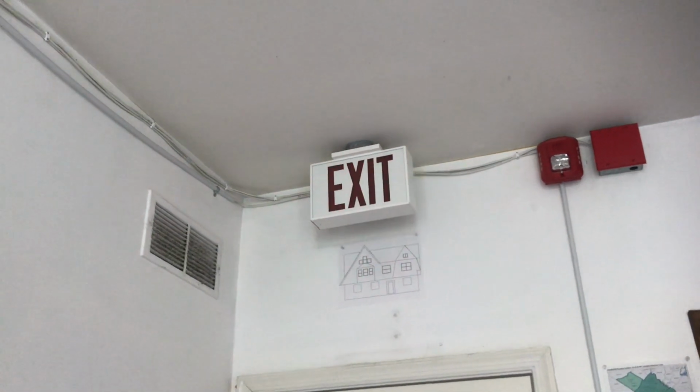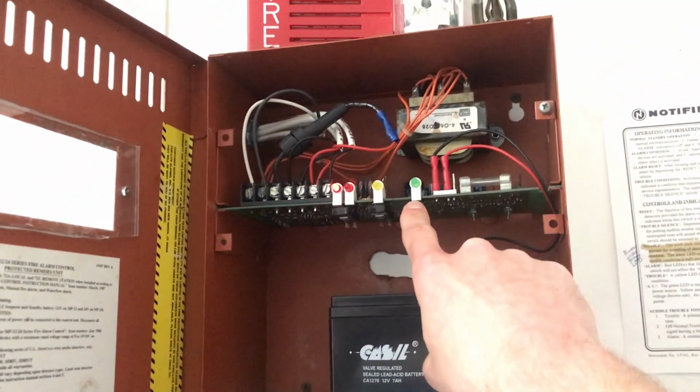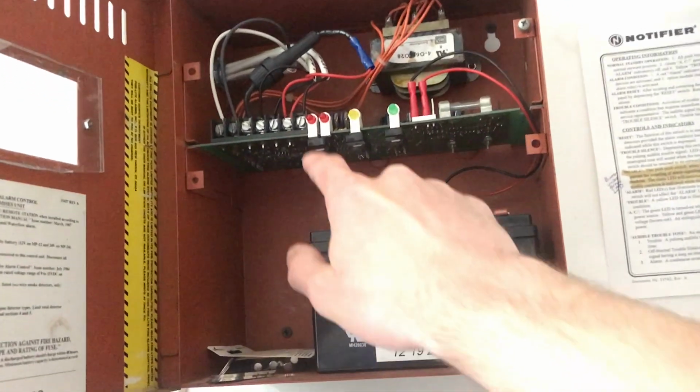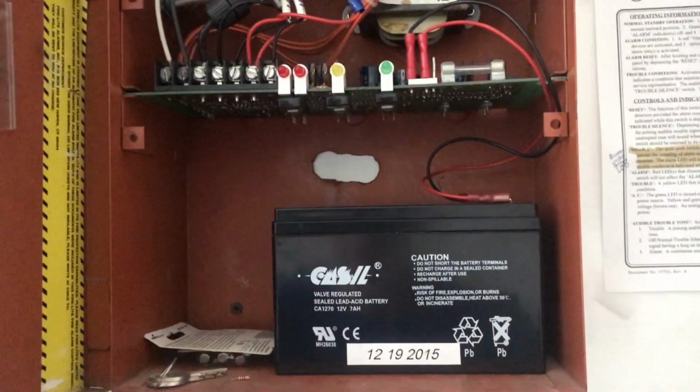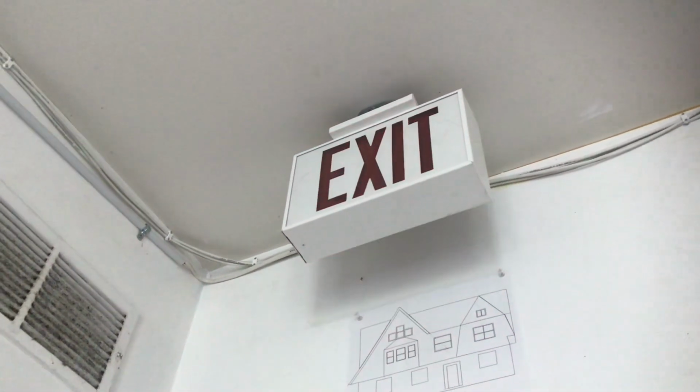You can see that flashes when the power goes out, and the emergency light's still on. Just temporarily let this orange strobe on battery backup. You can see, just on battery. I believe that battery should be replaced soon. It is about going on 5 years old. It will stay flashing. There is a setting on there for it to be constant. However, I kind of do like the flashing. Just plug this back in. And back to normal.